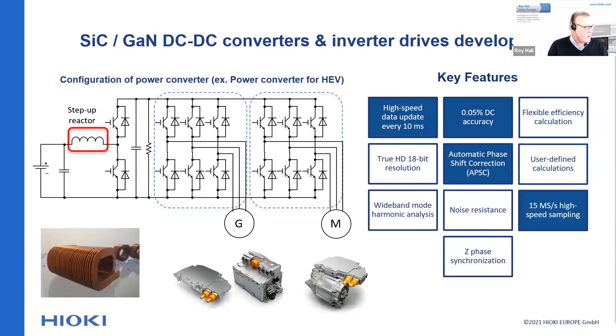Another application which was already mentioned is the SiC and GaN DC converter and inverter drive development. In those kinds of applications, there are reactors involved. As we have already discussed, the automatic phase shift correction function in that kind of measurement is very highly rewarded and essential to have an accurate measurement. So for this kind of application, the high automatic phase shift correction is important, the high accuracy at DC, but also the high accuracy at 50 or 100 kilohertz. The instrument also performs excellently at those high frequencies. Further, the update rate of 10 milliseconds is important because then you get more information about the dynamic behavior of your system.